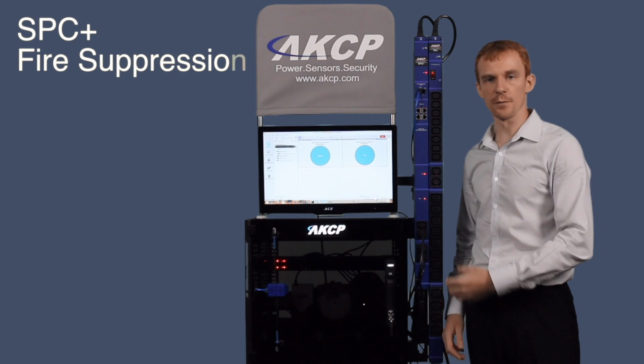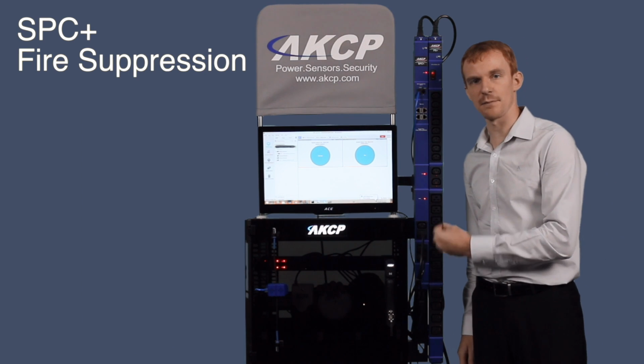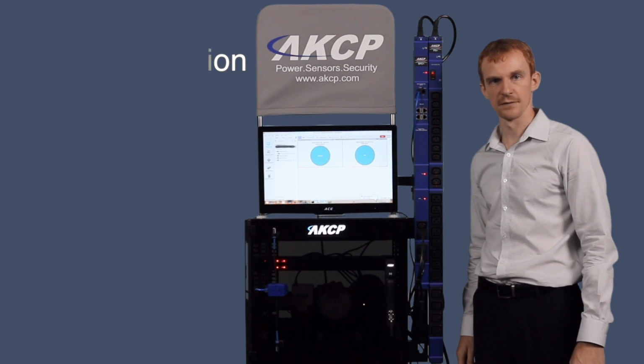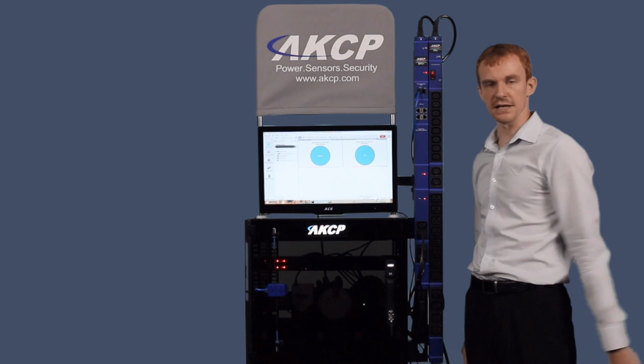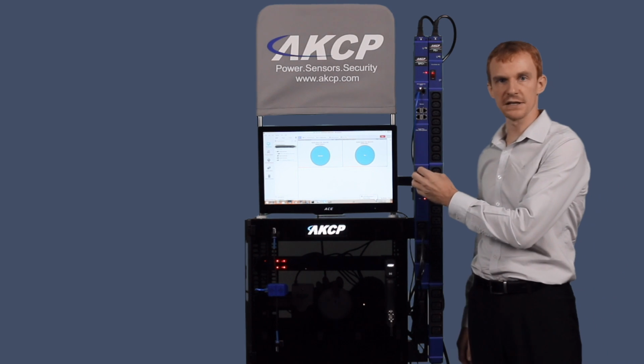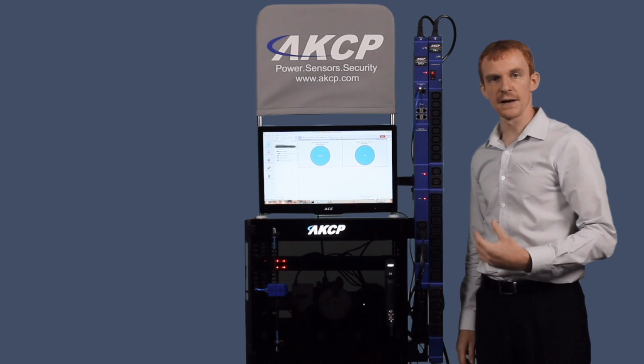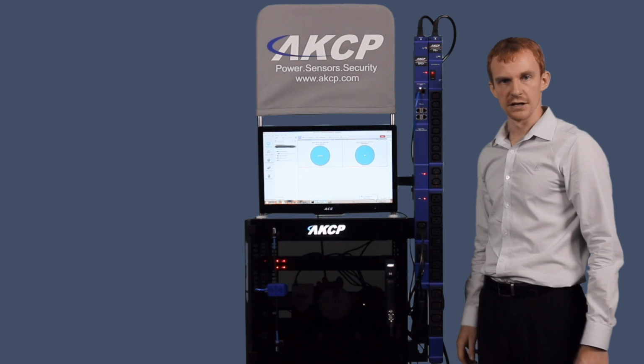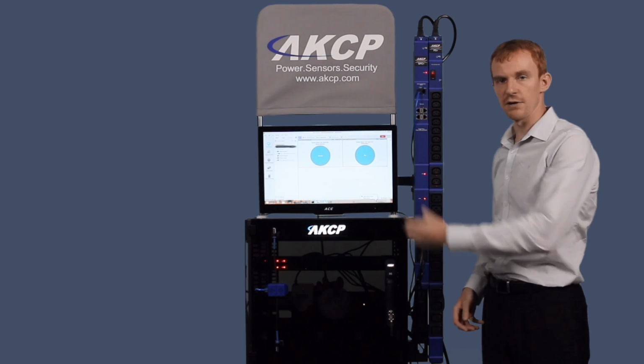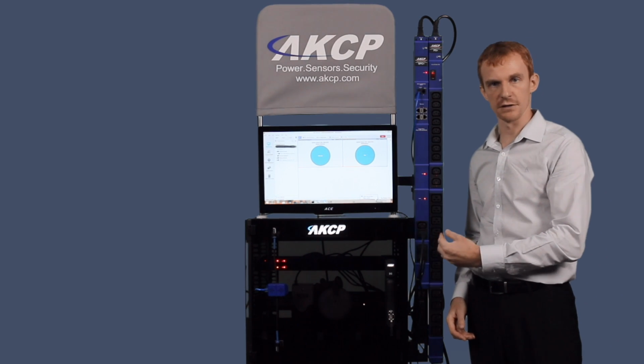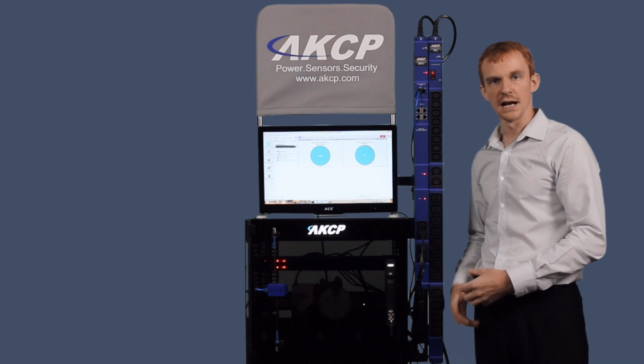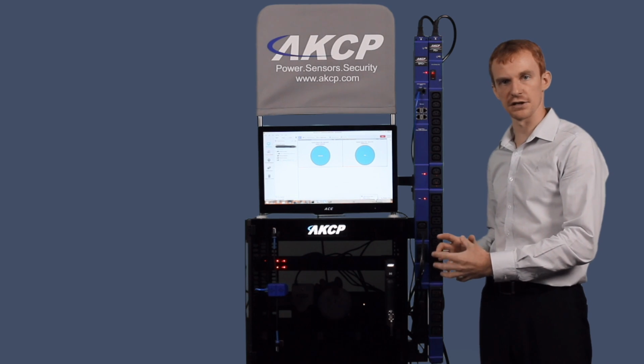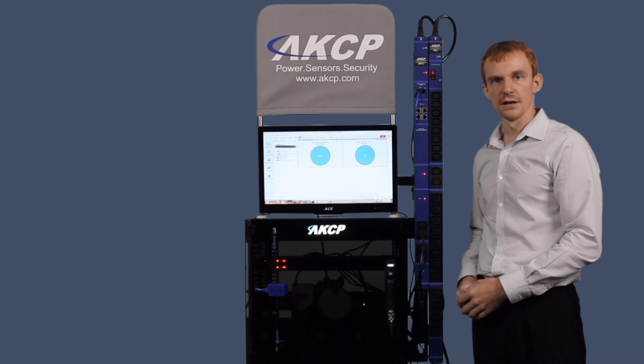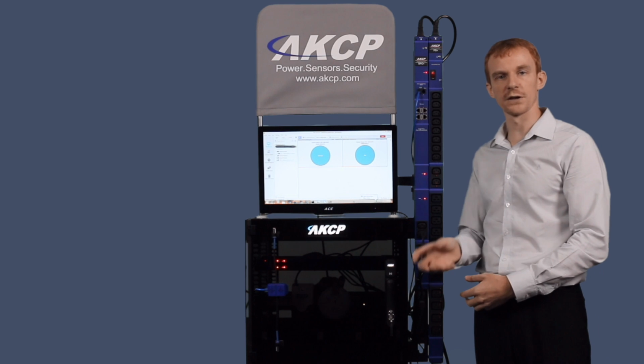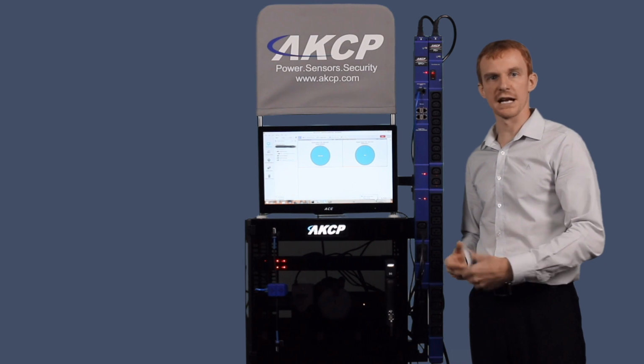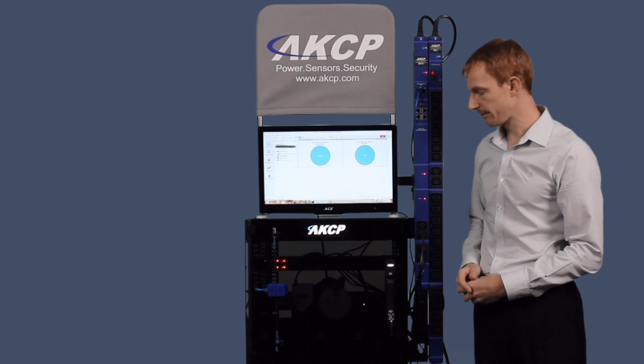SPC Plus incorporates AKCP's patent-pending fire suppression technology. By integrating a smoke detector in the cabinet with our SPC Plus power relay, in the event of a critical situation such as a fire within your cabinet, we can bring down the power to the cabinet, removing the source of energy and thus helping to contain the situation to a single cabinet. No longer do we have to flood the whole data center with potentially dangerous gases.